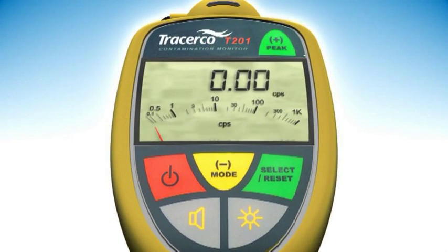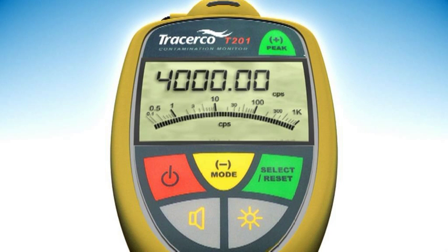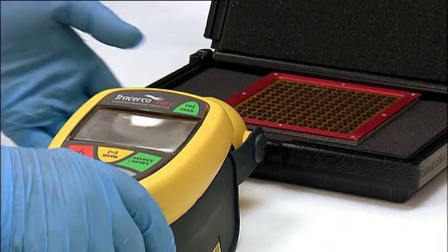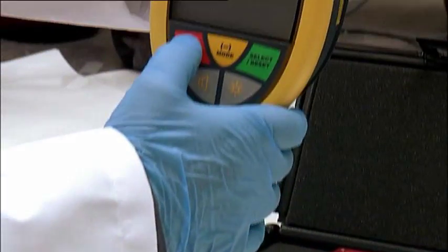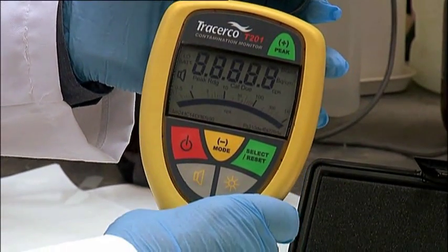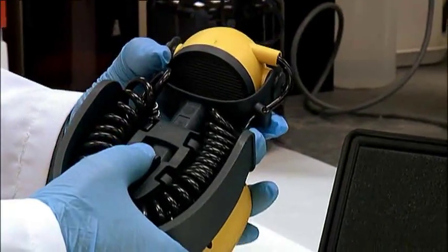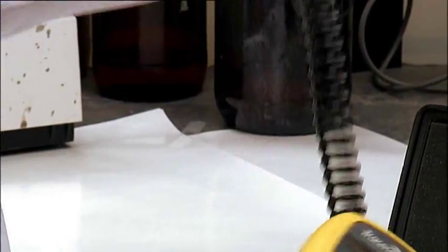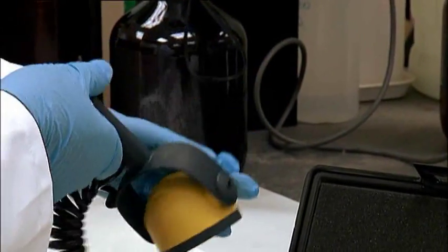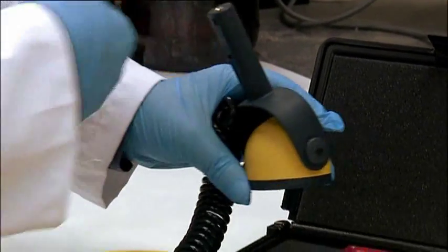The analog scale of the monitor displays from 0 to 1,000 counts per second, and the digital scale from 0 to 4,000 counts per second. To measure surface contamination, first switch on the monitor and place the probe approximately 3 mm above the surface to be measured. This appears difficult, but after a little practice, with a spacer of the right thickness, it should be second nature to achieve the correct separation.